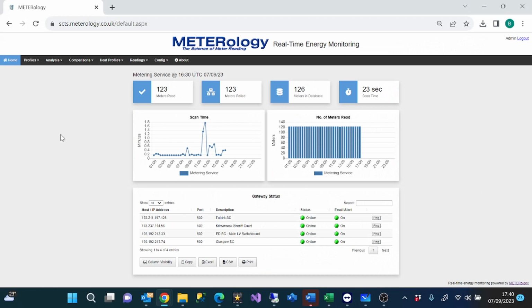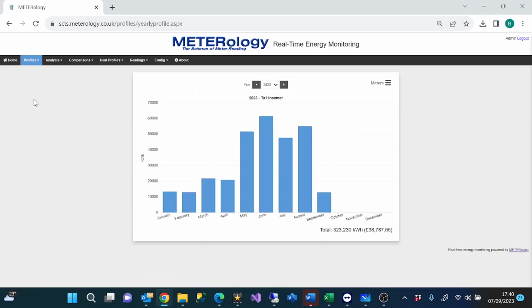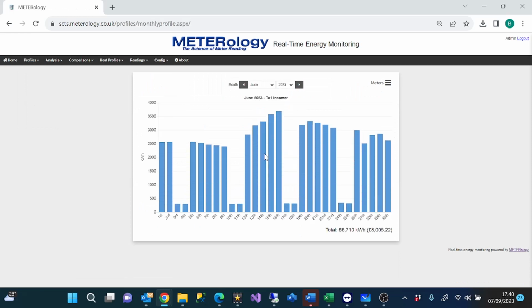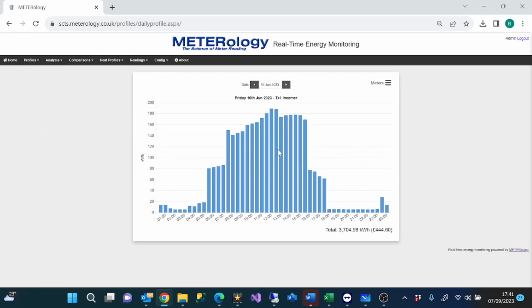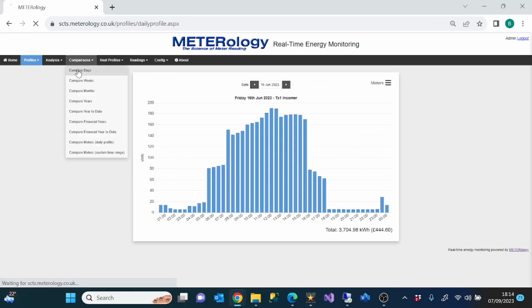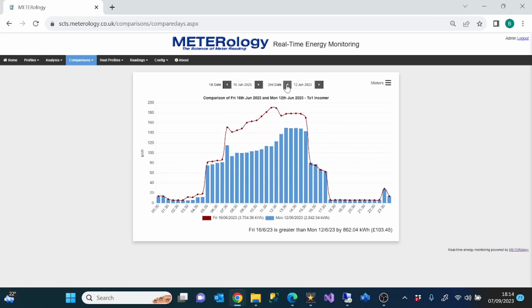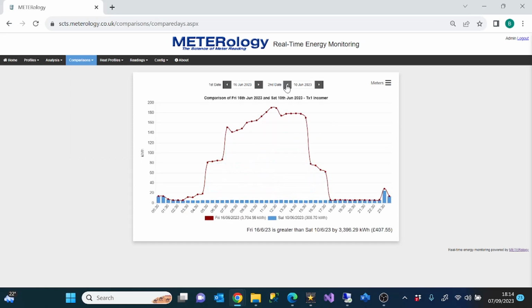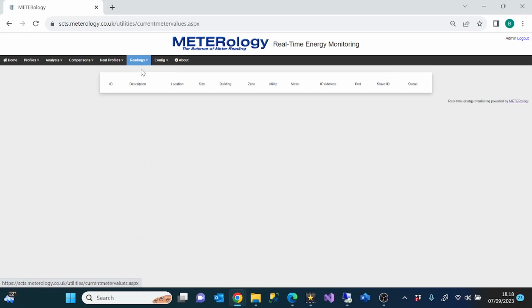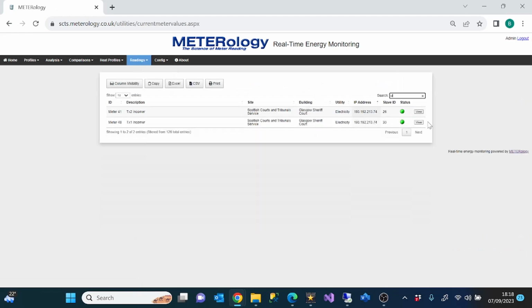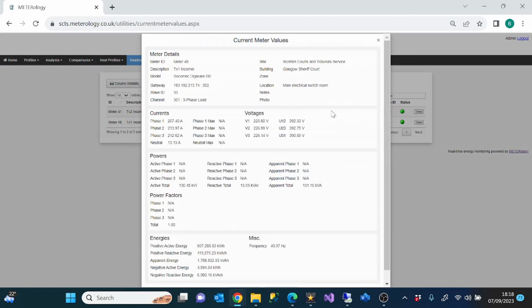This database would then be connected to a dedicated METERology real-time energy monitoring system, and this system would allow you to monitor and analyse data on an annual, monthly, weekly and daily basis. You would be able to compare different periods and different meters, and you would be able to interrogate each meter on demand, showing current, voltage, power factor and energies just as you would if you were standing in front of the meter.